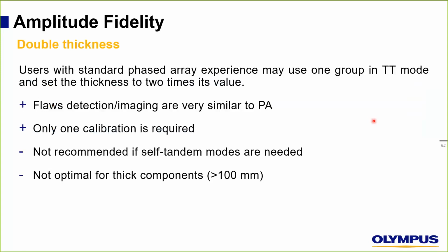Now let's talk about something that is trending on social media, double thickness. Some users with phase array experience and background may use one group in TT mode and set the thickness to 2 times its value. So they are creating something similar to phase array inspection. The plus of such a method is that flaw detection and imaging will be very similar to phase array. Only one calibration is required as well.